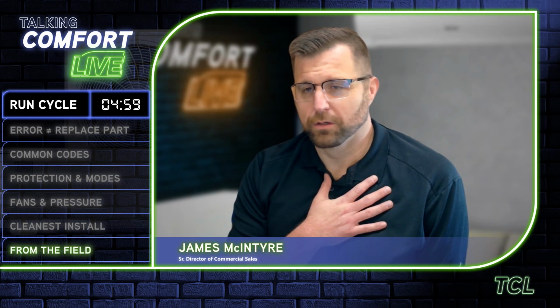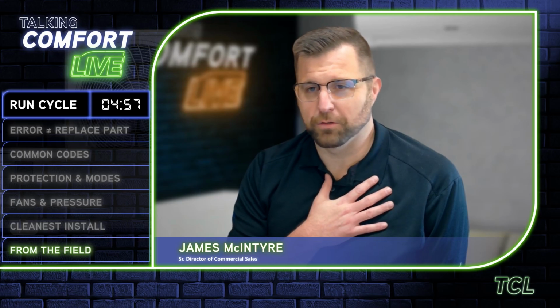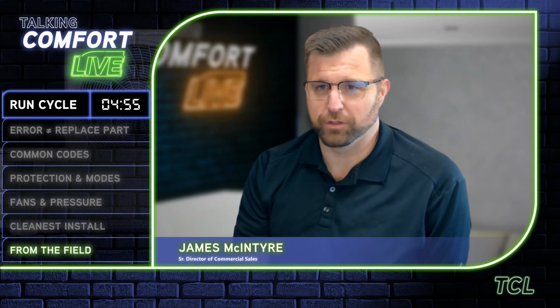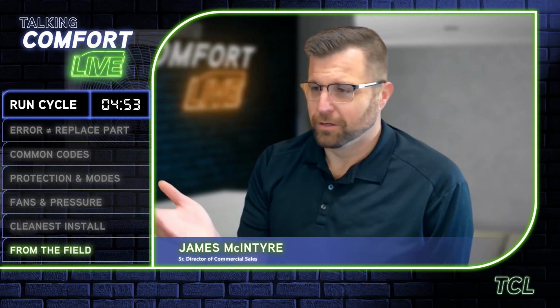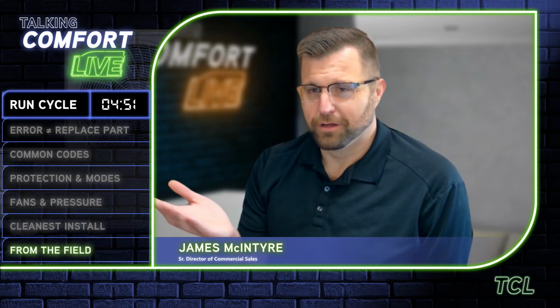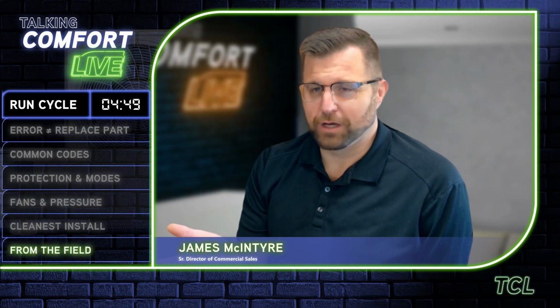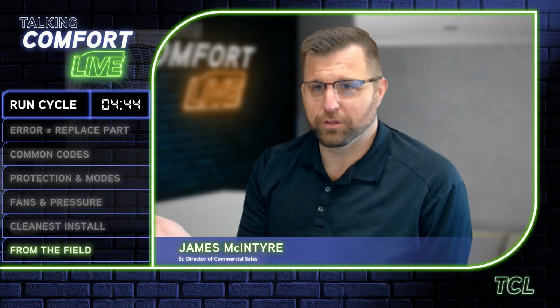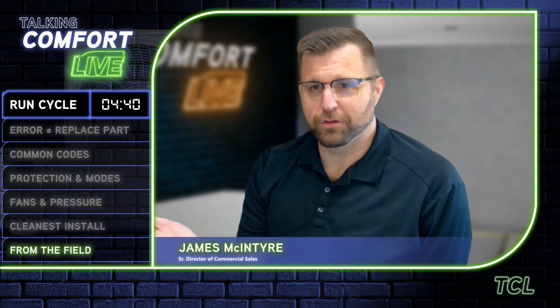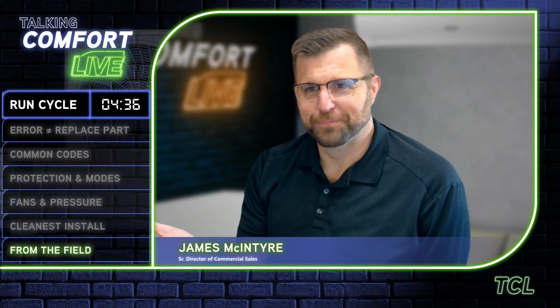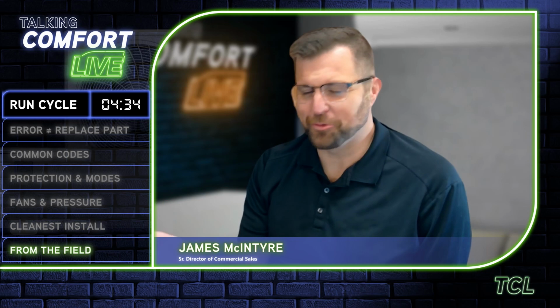Yeah. And believe it or not, I've taken commercial specs before and just went ahead and did the math because I saw that they would say the space is 1,500 square feet and it says 3 tons. That's weird. That's 500 square feet per ton. I go to the next space on the spec. It says 2,000 square feet. It says 4 tons. I'm like, huh, that's also 500 square feet per ton. Like, what are the chances? And then go on through the rest of it.